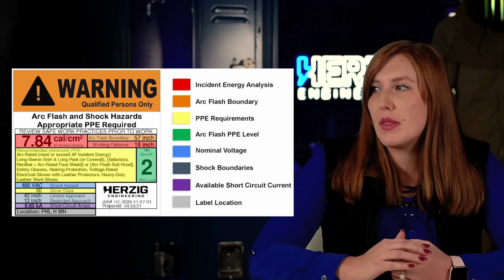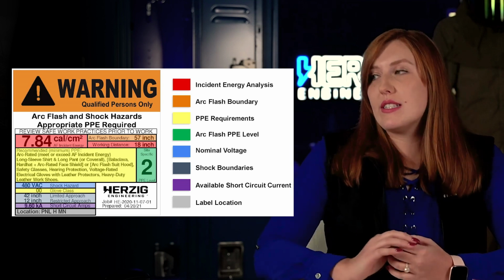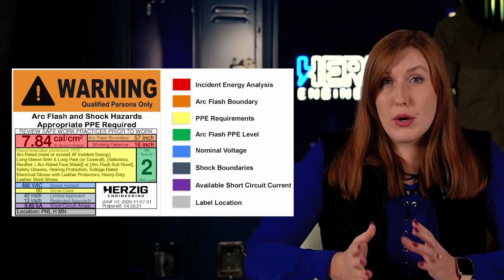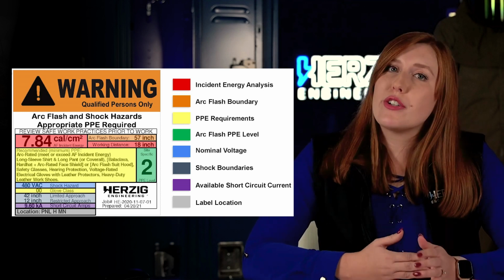And then just wrapping up with the panel name at the bottom. I will note it says warning at the top with an orange background. That's per the ANSI standards. If it's over a certain point of a hazard, typically 40 calories per centimeter squared is the cutoff, then that would change to a red background with white lettering that says danger. That's because most people don't have PPE rated for higher than 40 calories per centimeter squared of an arc flash hazard. So that's kind of the gist of what all the information is on that label, and why it's so important to go through not just what it is, but why you need to know this. How does it apply to you? And what do you need to do about that?